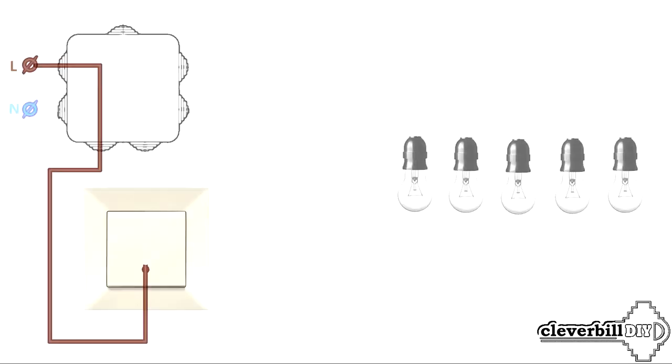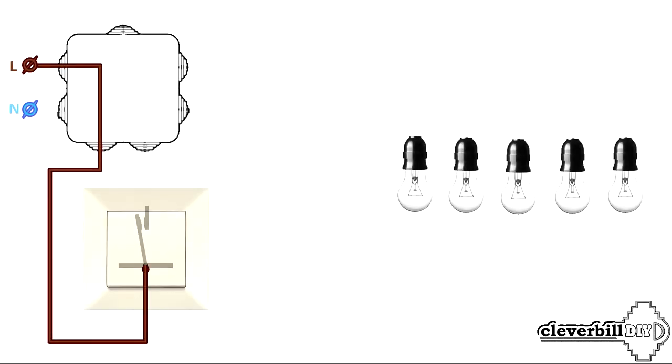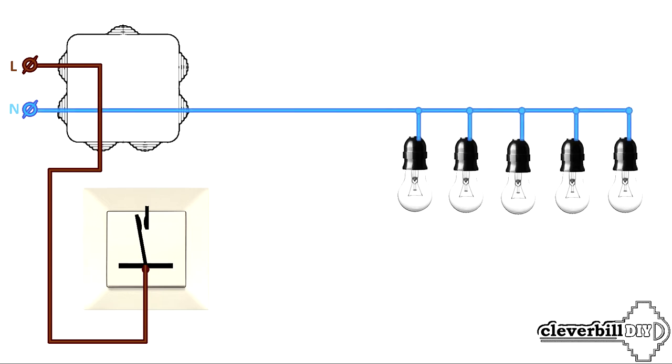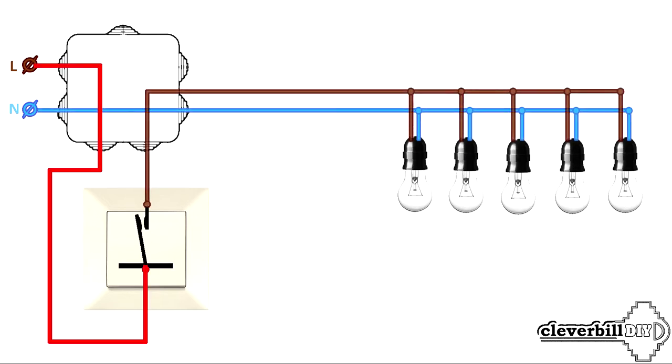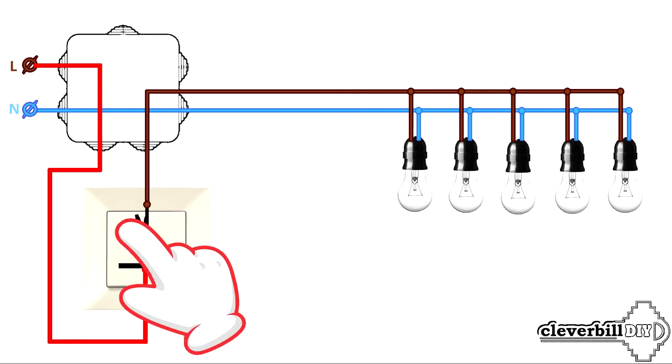If the light switch has only one button, then the wires coming from the horns are distributed into two bundles of wires, one of which is connected to the neutral wire of the ceiling, and the second to the wire of the L phase, where, in the same way, the phase should appear only after the switch button is turned on.